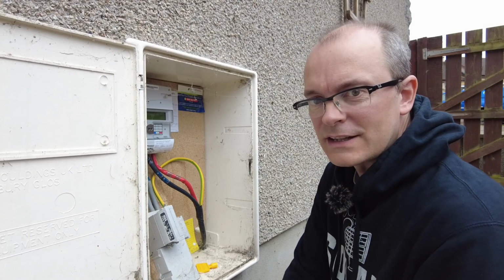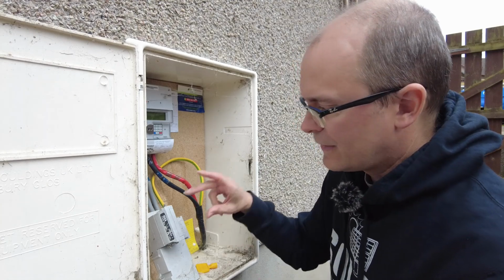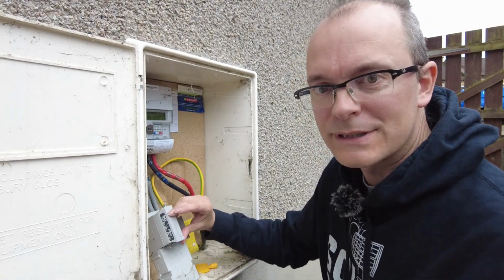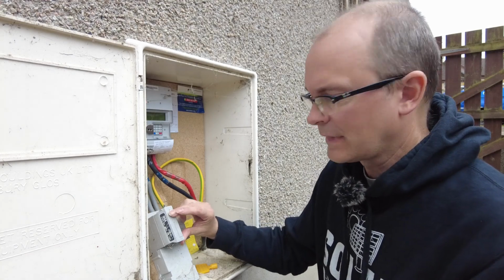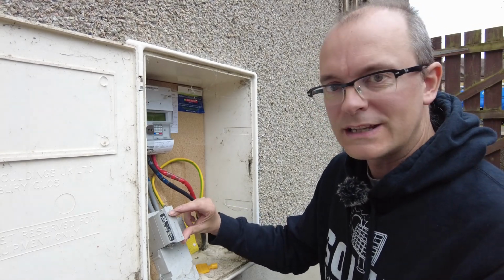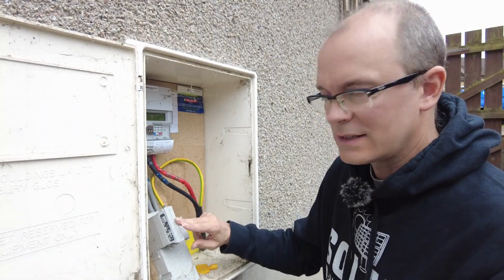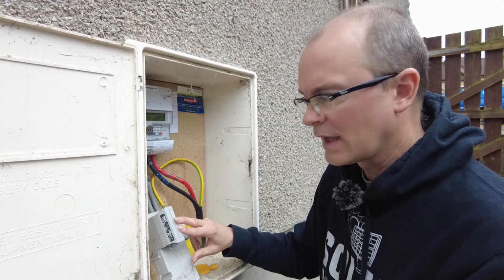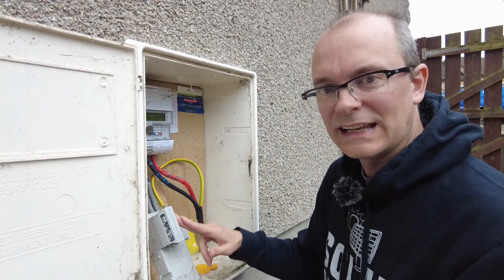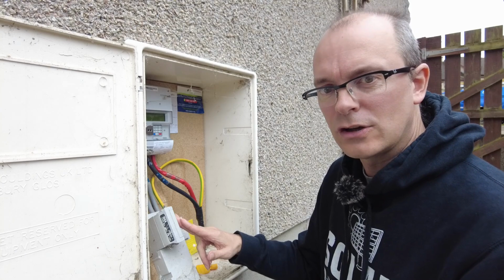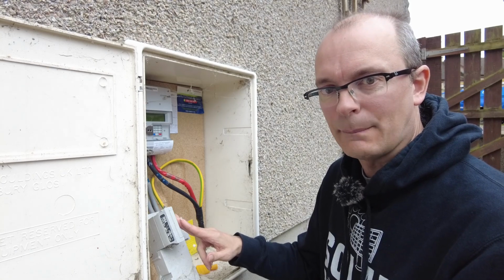Now, one misunderstanding is very common. This number here, 100 amps, cannot be trusted. This is the maximum rating of the fuse which can go into the DNO fuse cutout. The actual rating of the fuse in here could be quite different. It could be as low as 60 amps.